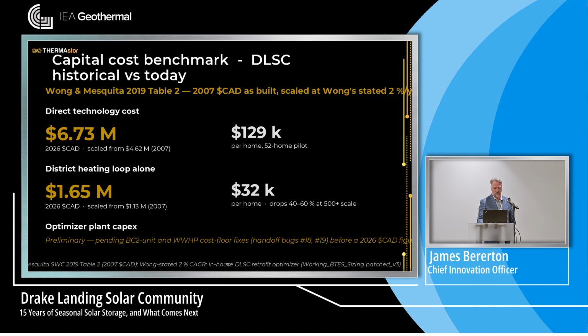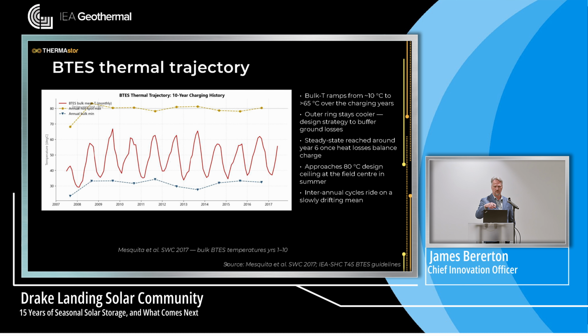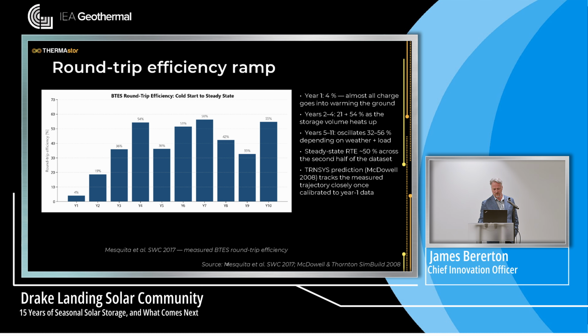That's how I got into all the renewable energy and the specialization in borehole thermal energy storage. So there you go, this is what the thermal cycle is over 10 years of measured data. You can see that first couple years just building up, and then it just cycles back and forth across the temperature regimes. The very high bar is what you would inject the heat temperature, so you'd inject at 80 Celsius, and the low bar is when you're pulling it out. That's how cold it could get. But the red is kind of the soil average temperature between the boreholes. I know I'm going very fast here, but this is a really interesting graph.